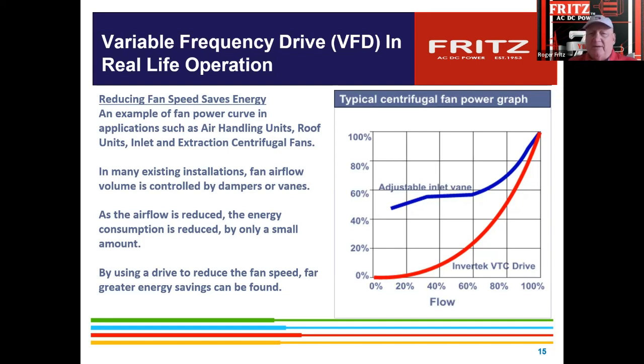So the motor is 0.8 times 0.8 times 0.8. It comes out to roughly about a 50% horsepower reduction, not a 20-point horsepower reduction, similar to what you do when you put a vane or a valve on. You get that extra saving from the VFD. You do have a 1 or 2% loss in the VFD, because you don't get anything for free. It does have a few losses in it, but the overall efficiency is quite dramatic.